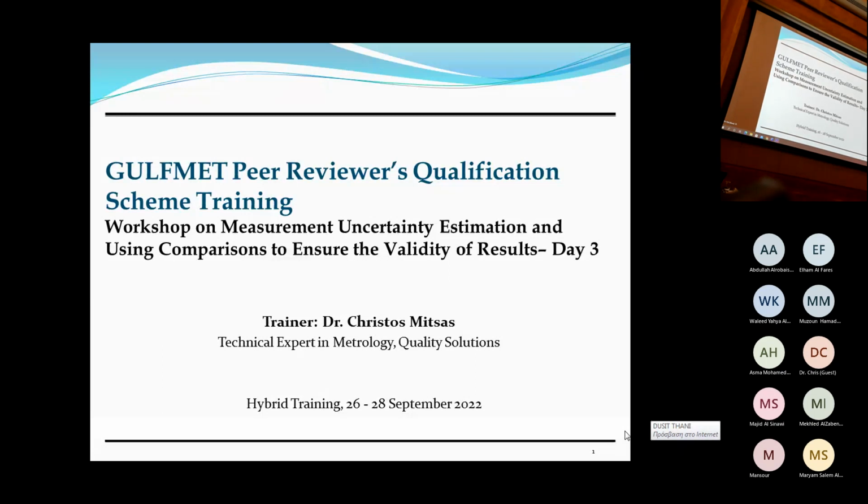The resolution contributes to the uncertainty, but it doesn't present a correction that has to be made. So there's no correction that we make because of limited resolution. However, we do include it in our uncertainty budget. So the expectation in this case is 0. So errors whose expectation is 0 are entered with left and right endpoints, rectangular distribution.